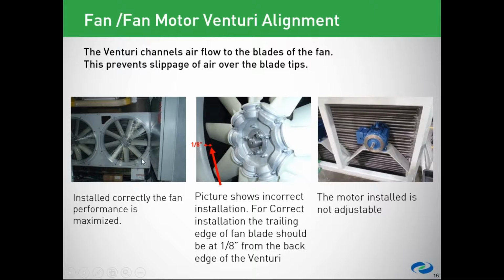So, the fan motor Venturi alignment. This is critical in airflow through the heat exchanger. The motors, once in position, are not adjustable. And the design of the support places it dead center of where that Venturi should go. The Venturi section is this section, and I will move my mouse here if you're watching, that goes around the outside of the fan blades.